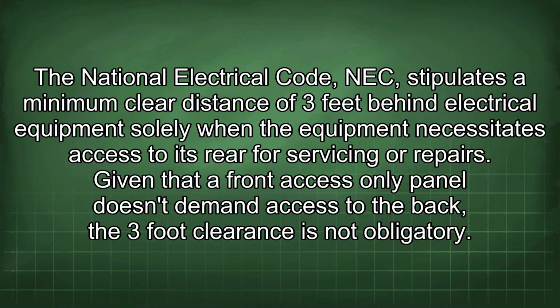The National Electrical Code (NEC) stipulates a minimum clear distance of 3 feet behind electrical equipment solely when the equipment necessitates access to its rear for servicing or repairs. Given that a front access-only panel doesn't demand access to the back, the 3-foot clearance is not obligatory.